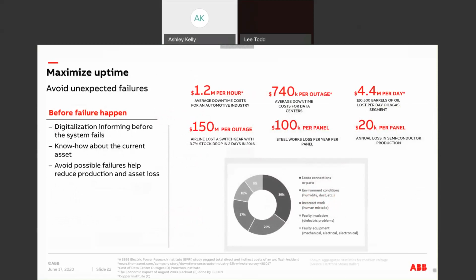Next, let's look at maximizing uptime and continuity of service. With digitization-based maintenance, the systems will inform you before an asset is about to fail, allowing you to plan when to change it. This is key. Without this, consider that you lose a charging motor on a circuit breaker, and that occurs at the worst possible time of the year—say, Christmas Eve. The motor itself might cost $100, which seems insignificant, but labor on Christmas Eve might cost you $2,000.